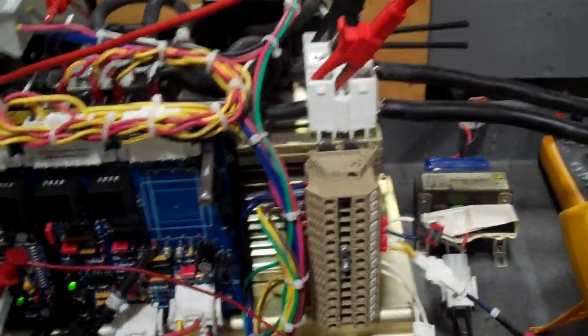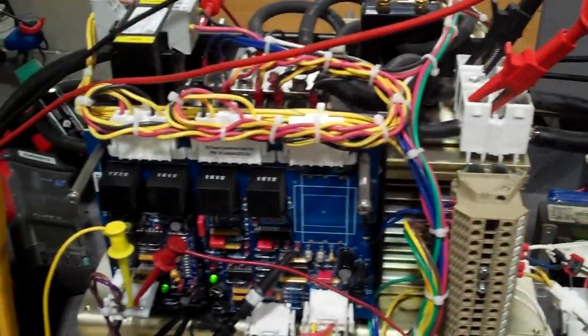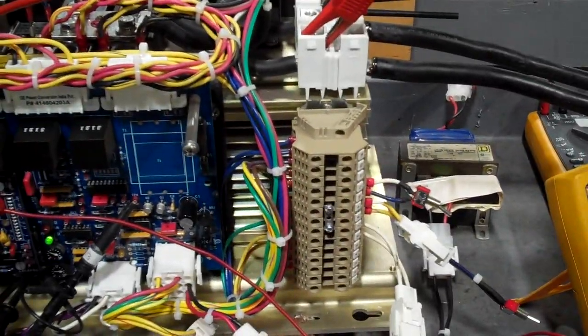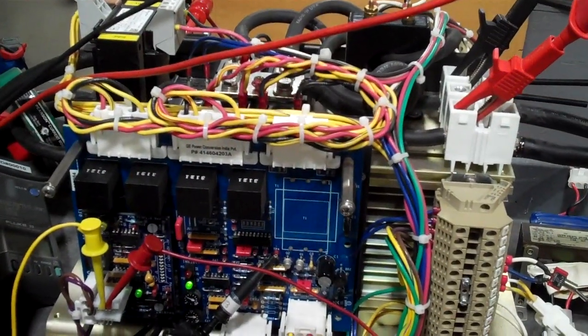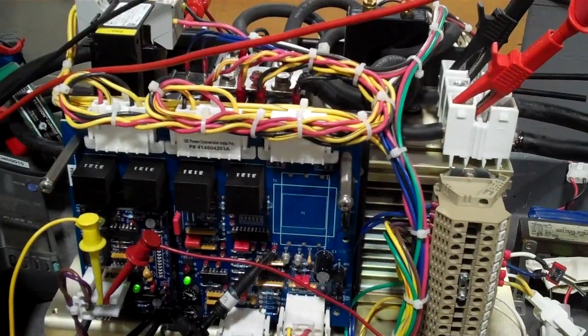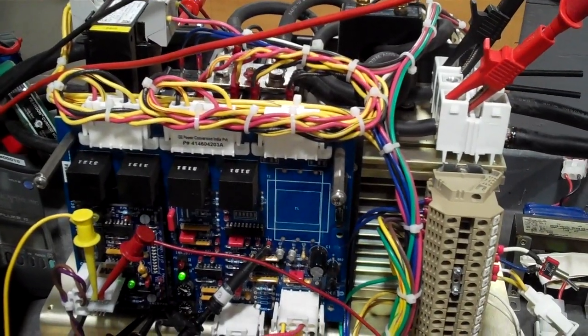Now, this is basically the end of the video, showing you that if we bring in the correct load, the CT is doing its job, and that feedback is going into the maximum current feedback. It's 1 volt. The maximum threshold is 2 volts. We could make a change there if we needed to, but overall everything is working fine. So this is the end of the second video.